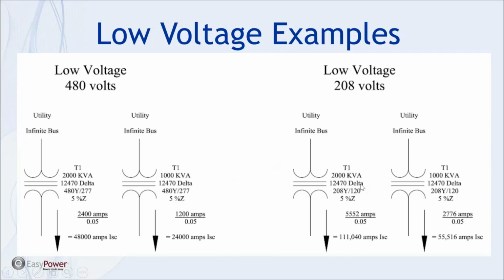One of the curious things that I have been really trying to educate folks to is lower voltage systems are not necessarily safer. You really have to be careful and have a notion of what size transformer you're connected to. So as we go from a 480 distribution system to a 208 system, if it's supplied by 2000 kVA at the same impedance, that available fault current now goes up to 111,000 amps on a 2000 kVA transformer. And with 1000 kVA, again, it's cut in half down to 55,000 amps. But a lot of the work that I do I don't see any fault currents hardly ever close to this. But they do exist at times, but the most I've seen is about 50 or 60,000 amps in practice.